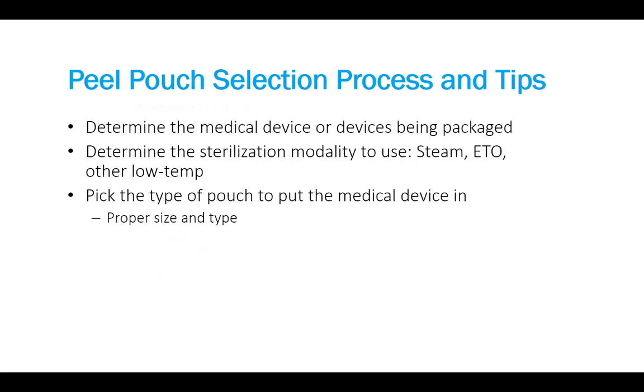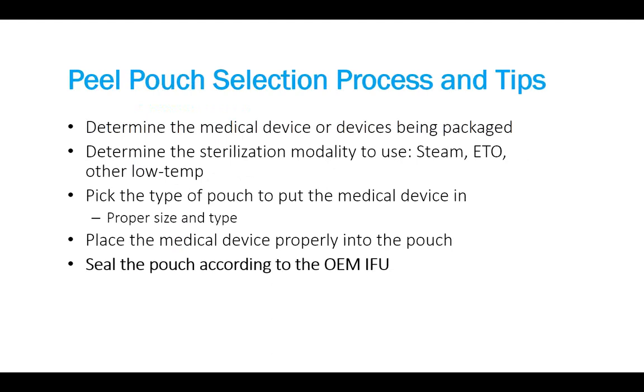You now get the proper size and type of the pouch. You place the medical device properly in the pouch. You seal the pouch according to the OEM IFU, making sure you have an inch, inch and a half around the device. Some people say the pouch should only be 70 or 80% filled with the device. Again, work with what your OEM says. Follow their IFU.